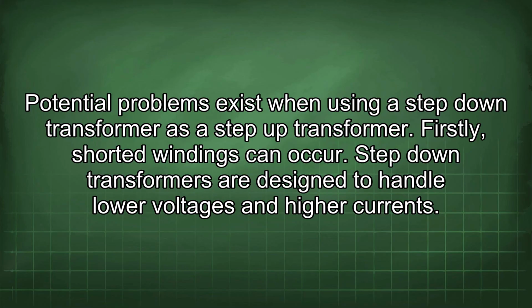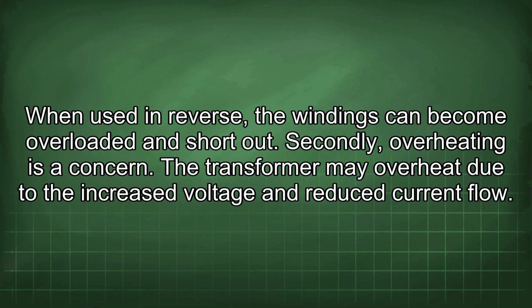Potential problems exist when using a step-down transformer as a step-up transformer. Firstly, shorted windings can occur. Step-down transformers are designed to handle lower voltages and higher currents. When used in reverse, the windings can become overloaded and short out. Secondly, overheating is a concern. The transformer may overheat due to the increased voltage and reduced current flow.